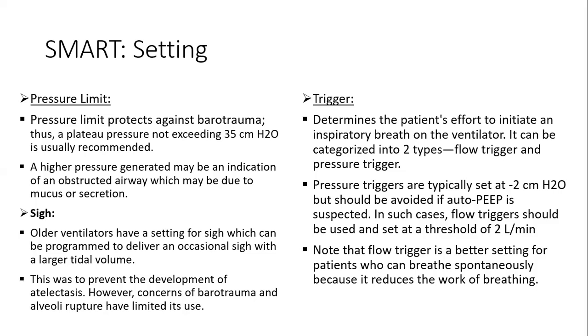That's what they call sigh. Most modern ventilators do not have this feature, but for academic and historic purposes, I just decided to bring it here. Sigh is programmed in the machine to deliver an occasional breath with a larger tidal volume. This is to prevent development of atelectasis, but it is also fraught with concerns of barotrauma and alveolar rupture, which has limited its use.